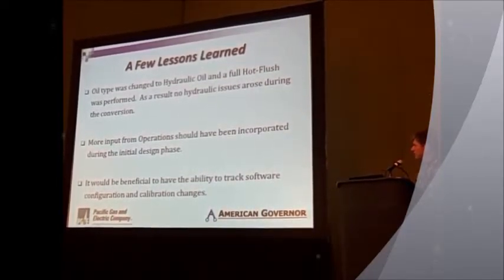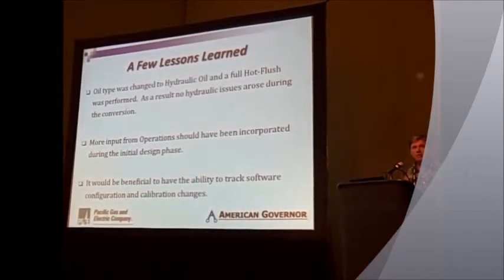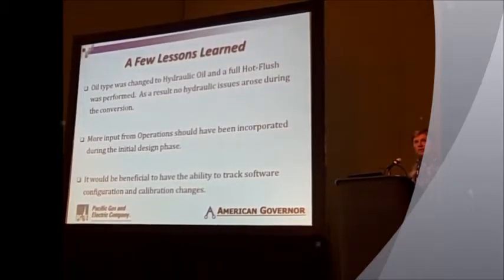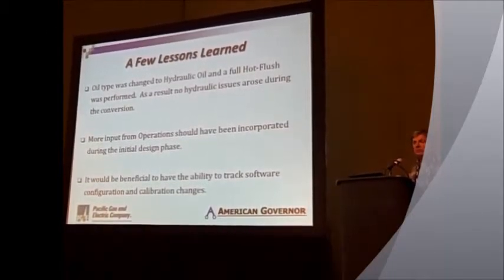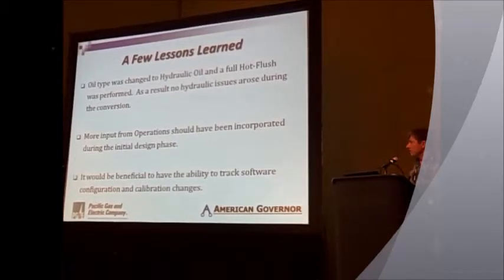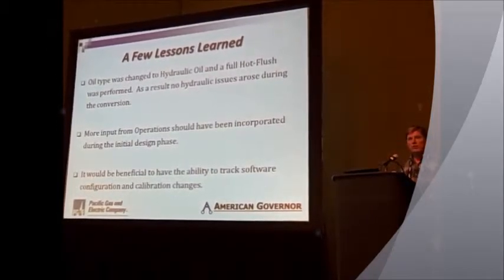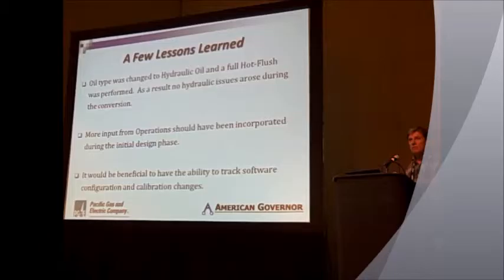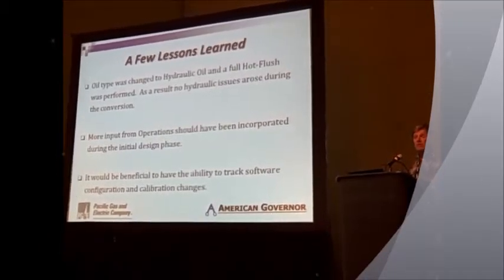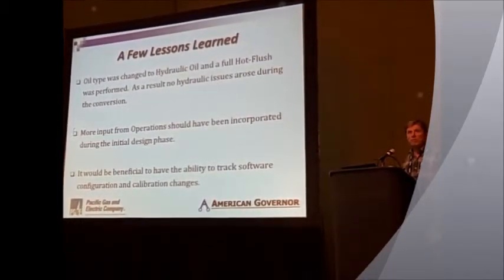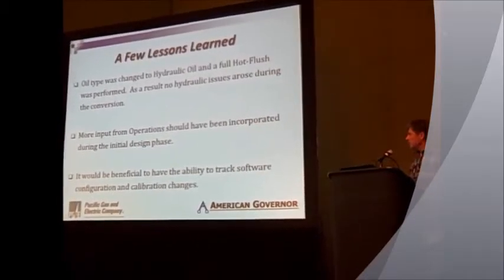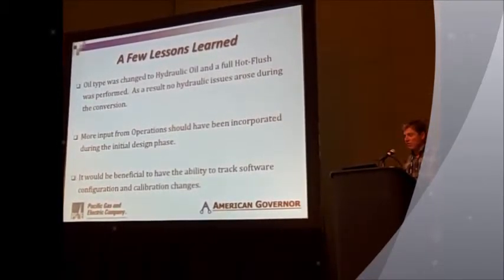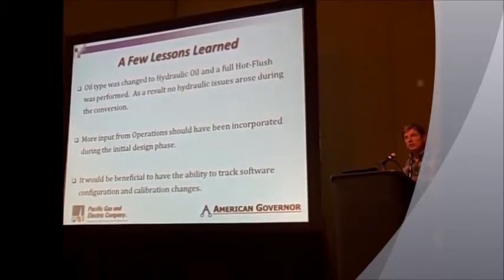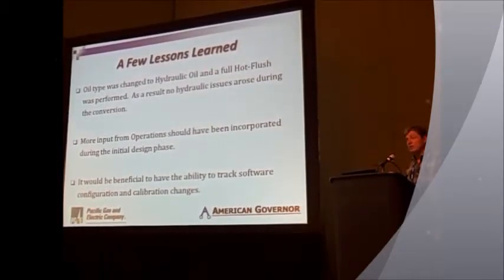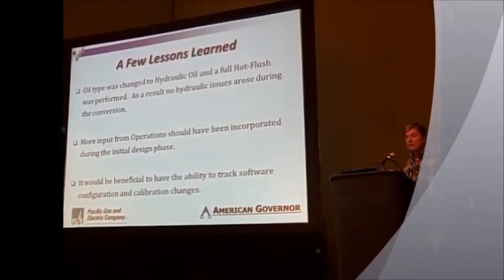And the last one: we had a little issue about a year after commissioning where one of the control parameters had changed, and we don't know how it changed, and it resulted in the needles actually closing on a unit trip, but the sensing didn't see that the needles had closed, and so we motored the unit for a few hours. Matt and I have been talking about that and changing the software so that it tracks those changes and allows us to see when the change was made and even potentially alarms when the changes are made.